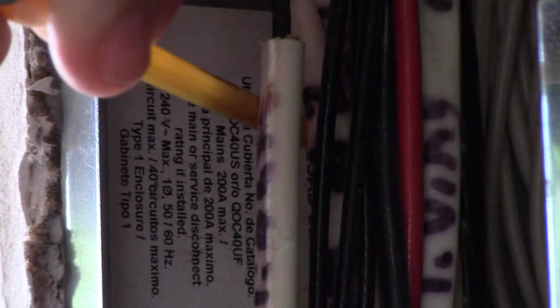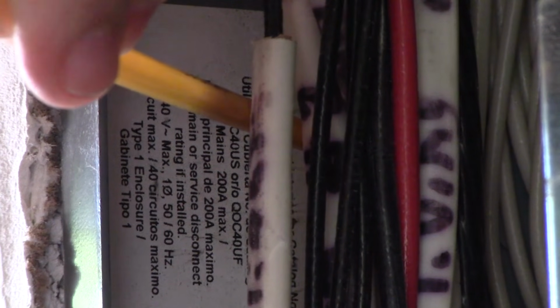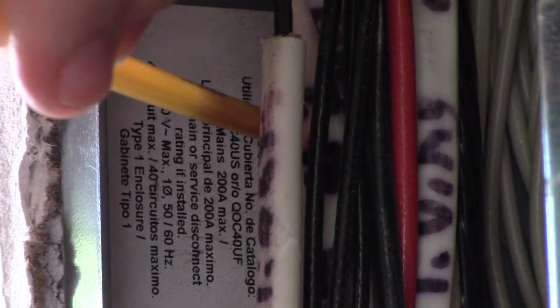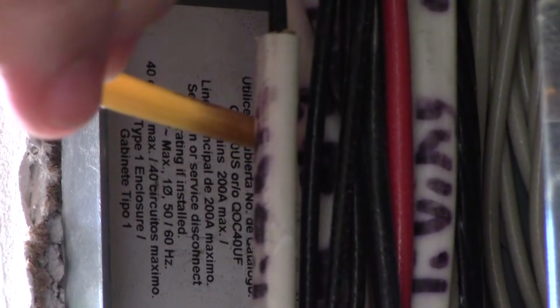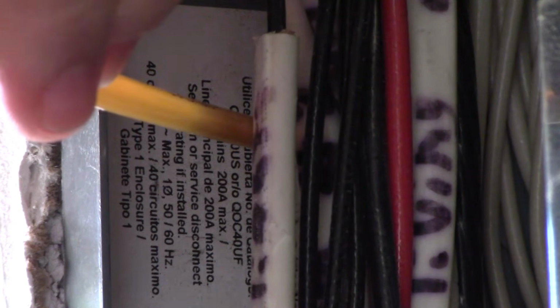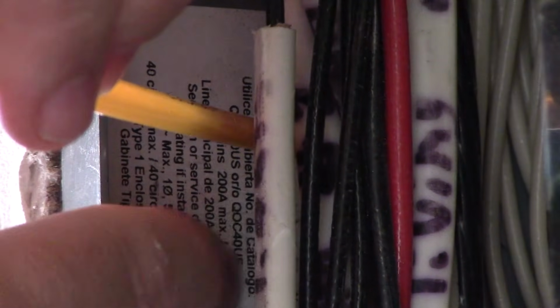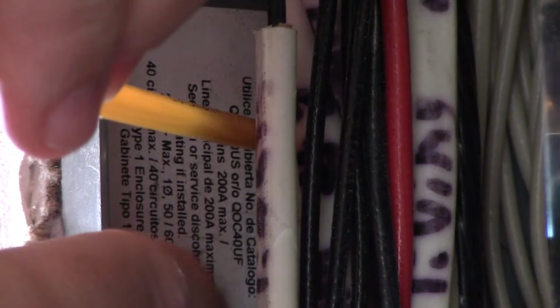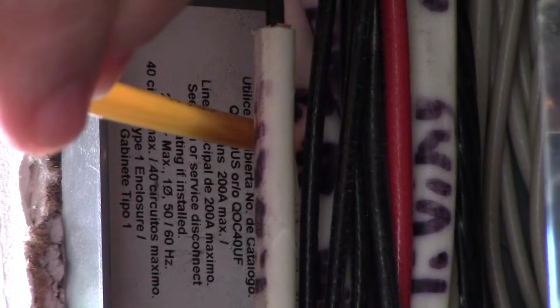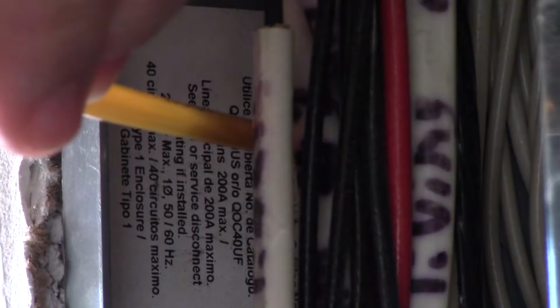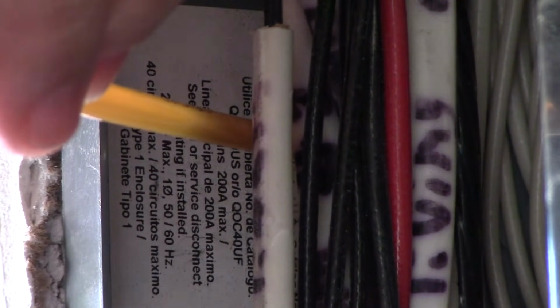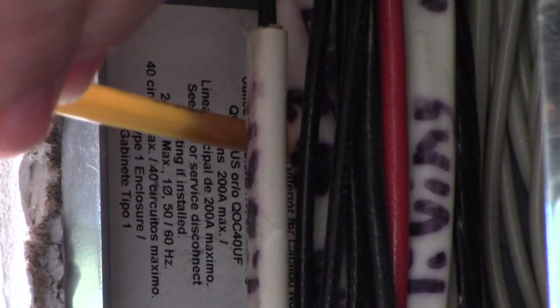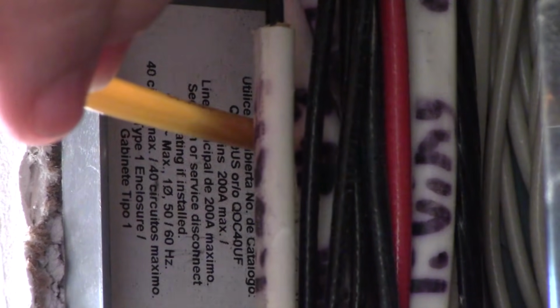So that's going to tell you. You might find this in a panel that says 150 amps here, and it says maximum 150, and then you come over to the main breaker and it has a 200 in it. Obviously, that's something that you're going to know this is the weakest link. That means that right here, it says that this enclosure is rated for 150, so somebody has changed the main breaker. But here it says a maximum is 200. Now, if this is 200, I could have a 150 main breaker in here. That would be acceptable, because the enclosure is rated for more. Again, your weakest link is going to be this main breaker, which is only 150. Okay, but here it gives us that information right here.